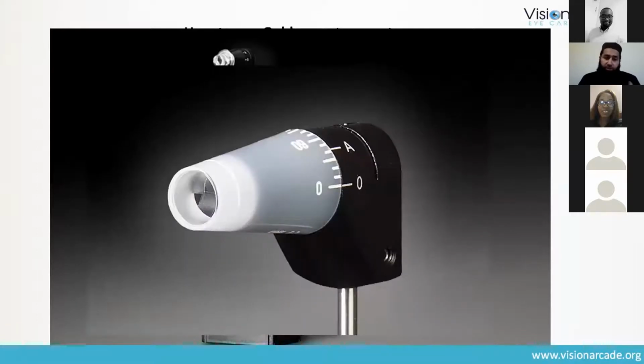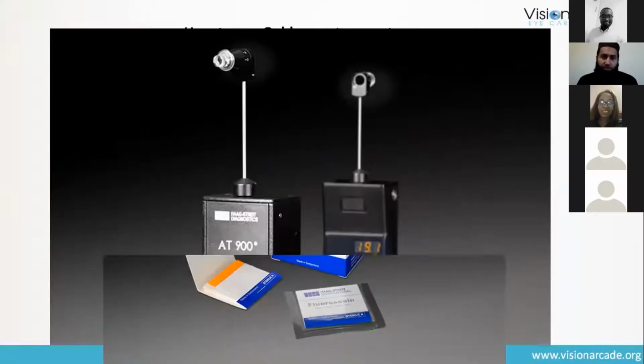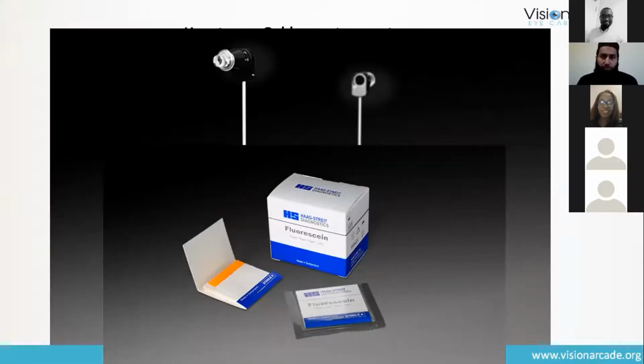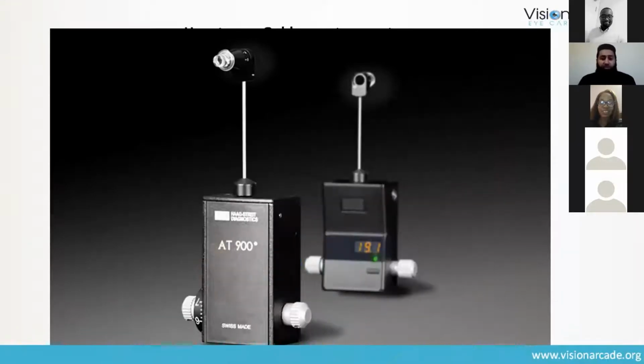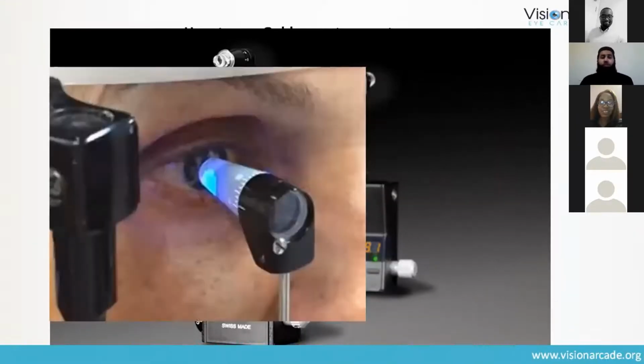When you're calibrating, make sure you use the prism which is provided by Goldmann, that comes with the Goldmann, not the plastic ones, the tonometer-safe ones. Use the fluorescein dye, put it in the patient's eyes, and make sure you give them some tissue as well, because if they have watery or runny eyes, it will be very difficult to perform the test. So once the patient's eyes are comfortable, you bring that Goldmann prism close to the patient's eyes, close to the center of the cornea, and then you take your measurements.